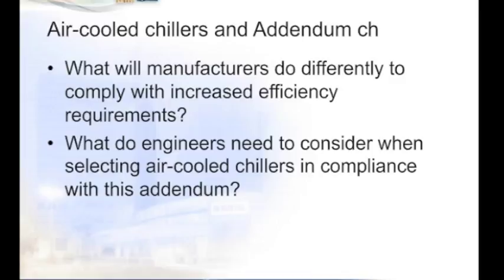For me, most importantly, let's discuss what engineers will need to do differently when selecting air-cooled chillers in compliance with the addendum requirements. Engineers need to start doing some legwork now so they have a complete understanding about which manufacturers have chillers which fully comply and which ones might be preparing to release equipment that will comply. As mentioned previously, the first cost for some of this high-efficiency equipment is important to consider as to how it affects the total project budget cost. So to provide a little firsthand insight, I discussed these higher efficiency requirements with an industry-leading U.S.-based chiller manufacturer and determined that they're able to comply with the higher efficiency requirements at both full and part load with only their highest efficiency chiller model. Now this is talking about air-cooled chillers only.